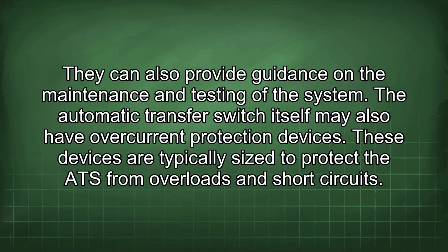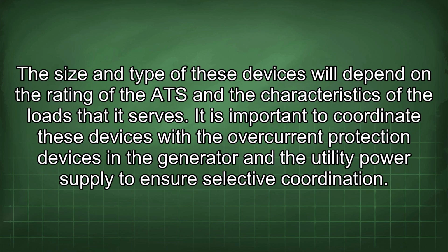The automatic transfer switch itself may also have overcurrent protection devices. These devices are typically sized to protect the ATS from overloads and short circuits. The size and type of these devices will depend on the rating of the ATS and the characteristics of the loads that it serves. It is important to coordinate these devices with the overcurrent protection devices in the generator and the utility power supply to ensure selective coordination.